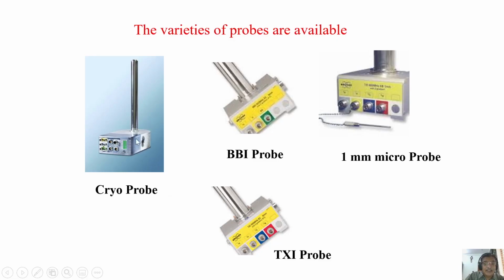Here, the instrument also has thermal noise. When you are detecting the signal with a coil, noise will also be picked up, thermal noise. So to prevent the thermal noise, we have a cryo probe where most of the coils and the electronics are kept at cryo temperature, so that the thermal noise is reduced, and you have a better signal to noise ratio. You pick up only the signals more. This type of probe gives at least 3 to 4 times better signal to noise ratio than the conventional probe. Theoretically, it should be 4 times more than a conventional room temperature probe.